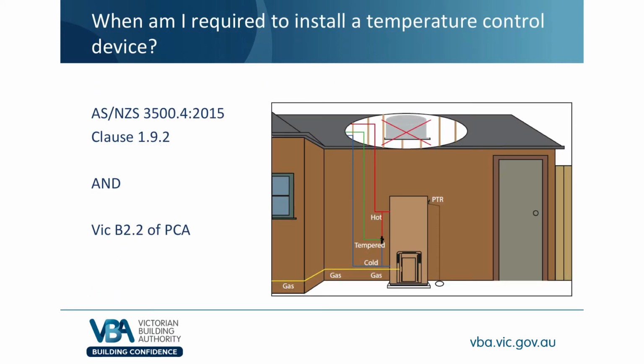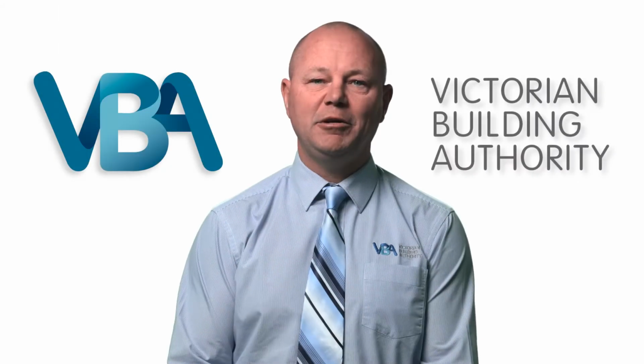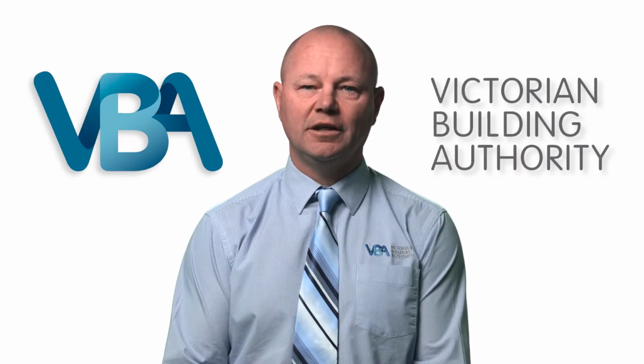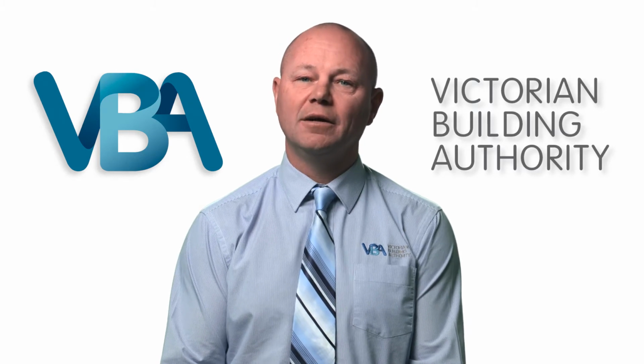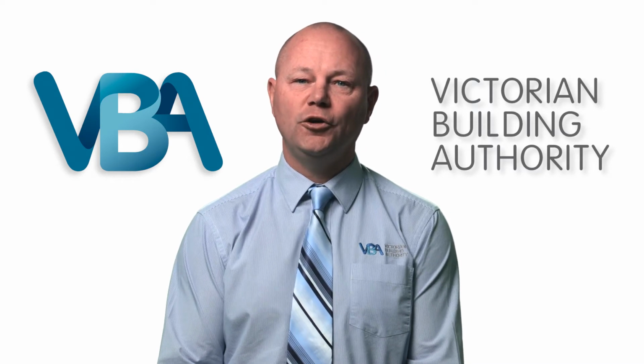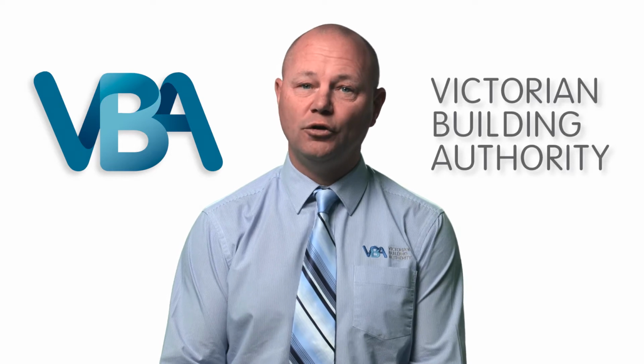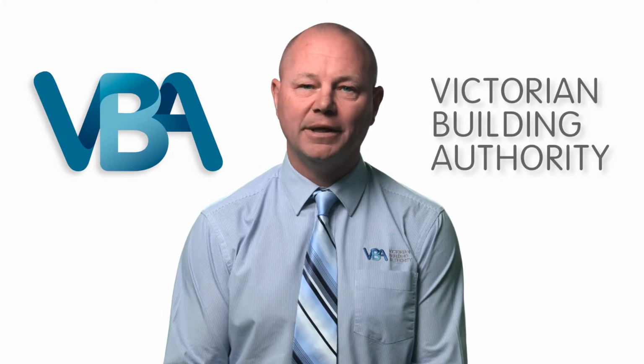Frequently asked questions. When am I required to install a temperature control device? Under the Heated Water Standard, AS/NZS 3500 Part 4, a tempering valve is required on all new heated water installations. It is deemed to be a new heated water installation when a practitioner either 1. Installs a hot water unit and hot water piping, or 2. Installs new hot water piping alone.